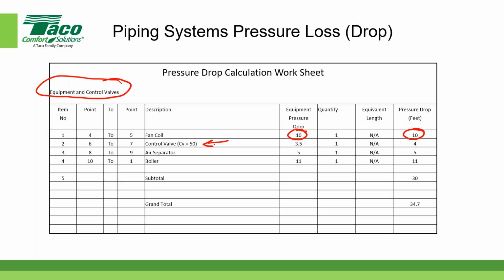Now, here's something we will provide some calculations for. If the control valve has a CV of 50, that means that valve will have a 1 PSI pressure drop at 50 gallons per minute. Is everyone in agreement with that, Brett? Yep. So now our actual flow is greater than 50 gallons per minute. It's actually 61.5, if I recall. So we have to use this equation. We have to say that the final pressure is equal to the initial pressure, I'm going to put PI here, times the ratio of the flow. In this case, we need 61.5 divided by 50 squared.